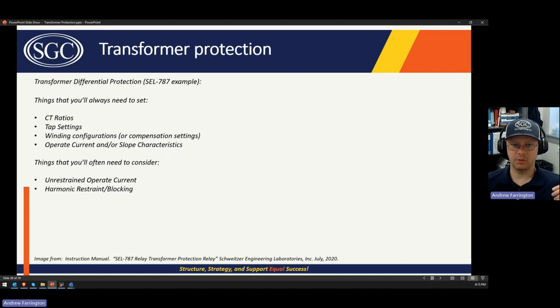Sometimes the operate current is so high that it's basically impossible or impractical that it would ever be a through fault current. And so the relay doesn't need to wait for the calculations of that slope characteristic, and you can just trip immediately. So that's the unrestrained operate current versus the restrained operate current, which is operating on that slope. And then you might also want to consider harmonic restraint or blocking settings, and we'll talk about that.